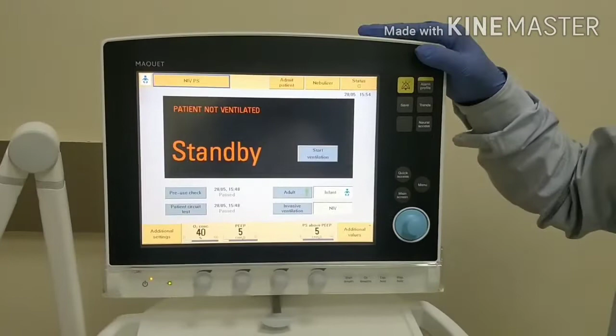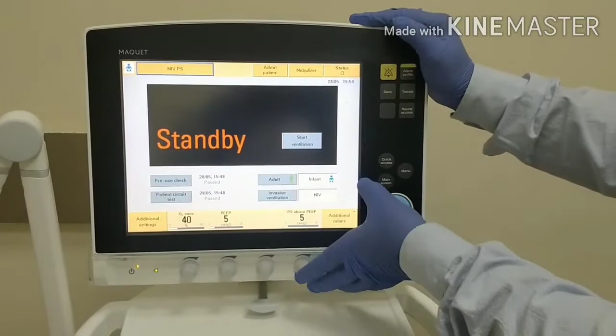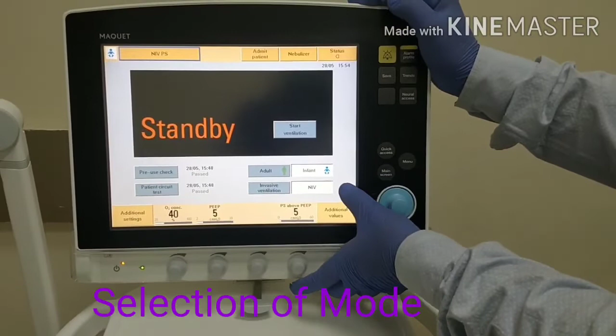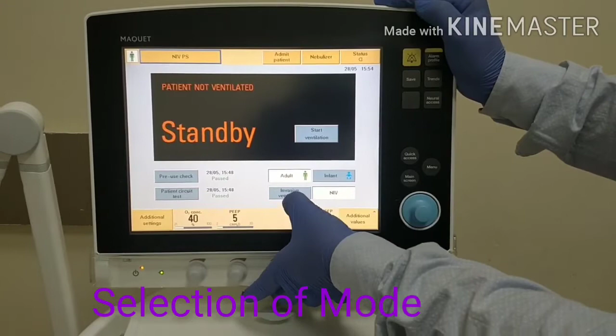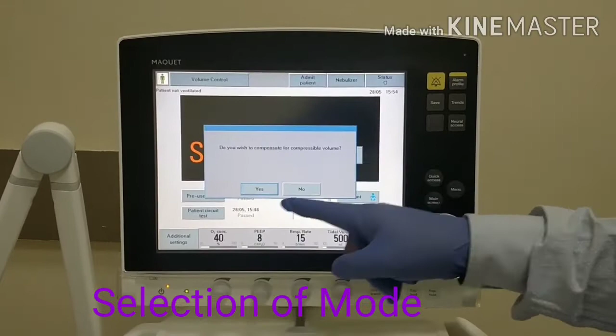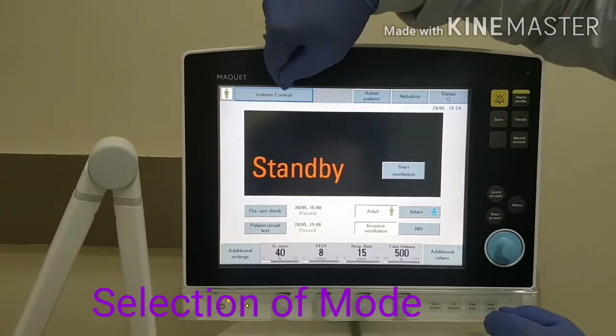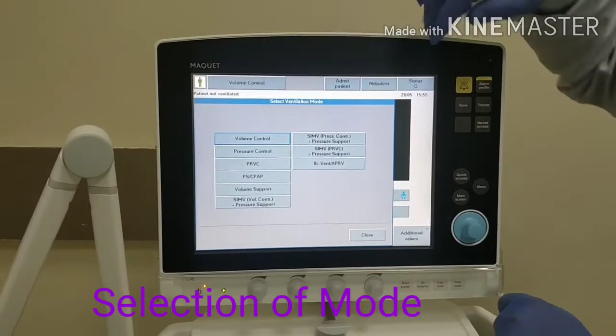Before connecting this ventilator to a patient, we have to select the type of patient. This ventilator has already selected infant patient and non-invasive mode. So now I will select adult patient and invasive mode. Do you wish to compensate for compressible volume? Yes. Now we have to select the mode. So press volume control, then press volume control mode again.